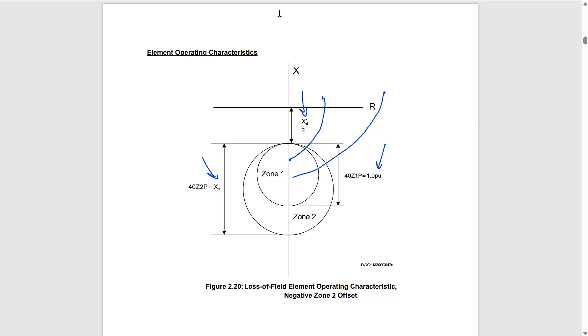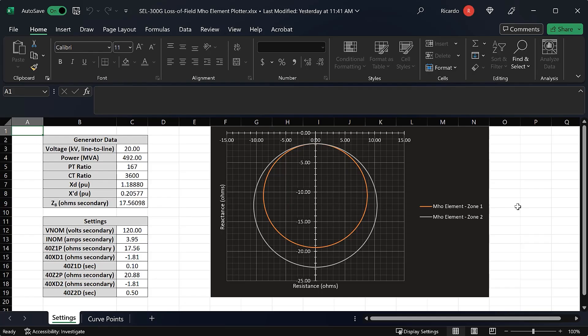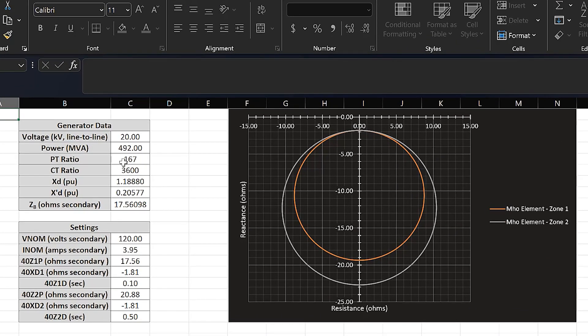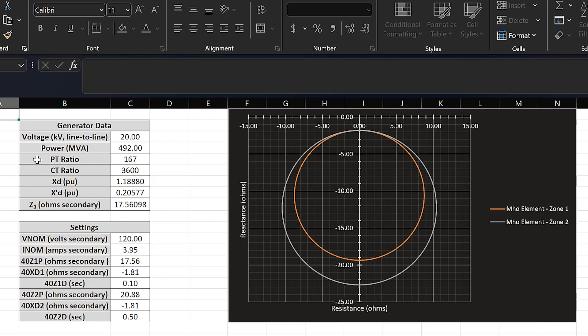Now let's look at the relay settings to see how we can set up this loss of field protection scheme. Before going into the settings file, I want to show you this spreadsheet I created which automatically calculates the settings for zone one and zone two based on user input. You can download this spreadsheet using the link in the description. You enter generator data in the top table and the spreadsheet automatically calculates the SEL 300G settings in the bottom table.